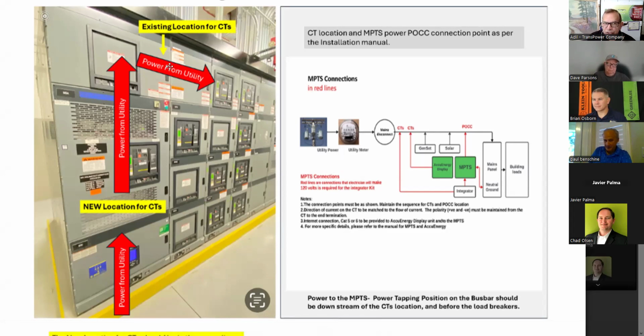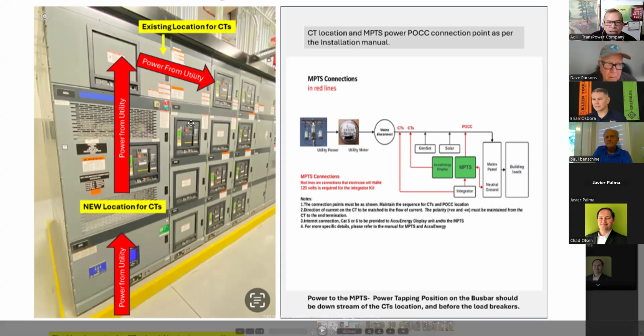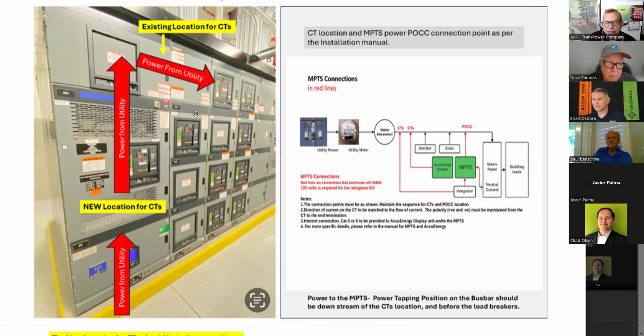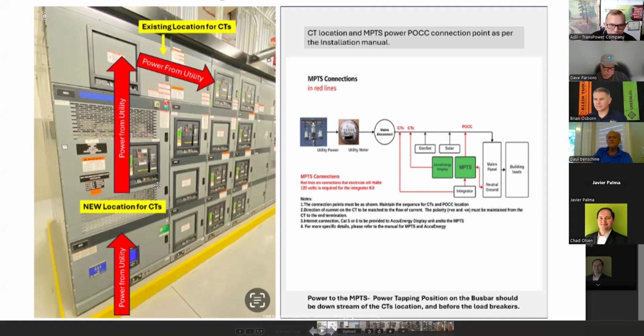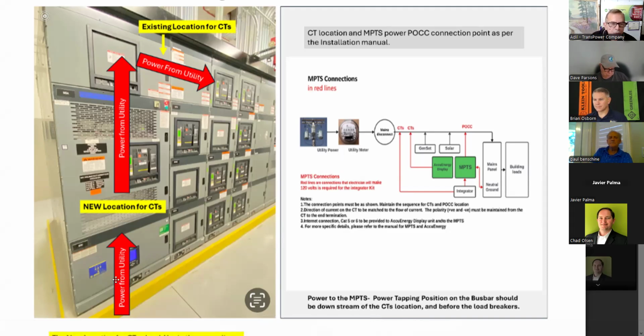The second time they did it, they installed it and squeezed it in on this panel, and they didn't realize that, see, this one is running this way and it's probably dropping down. So you're partially on the upstream side and partially on the downstream side. This was the third time. We said your existing CTs, that the second time they installed here, need to be moved down here, because there is a nice panel below this main switchgear. It's coming in here. Either open this or open this and install it here. And that's what they did last month. So this unit was installed in December, and for 8 months, we didn't have power management data.